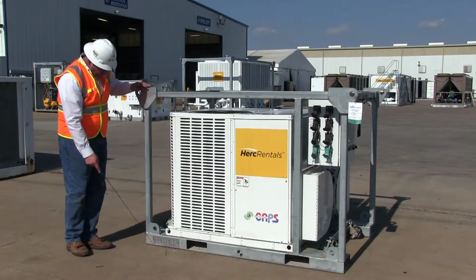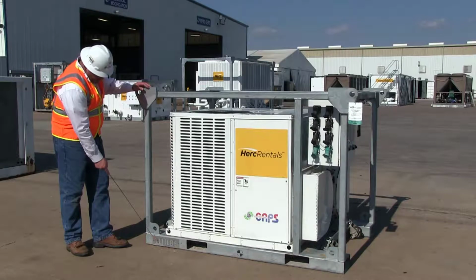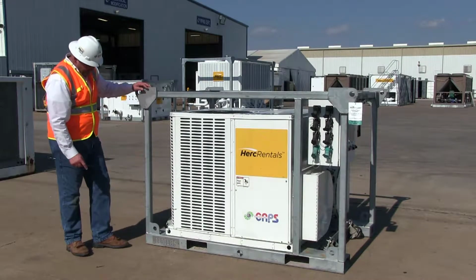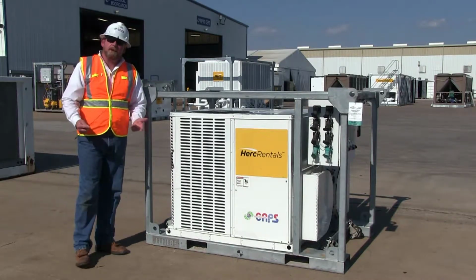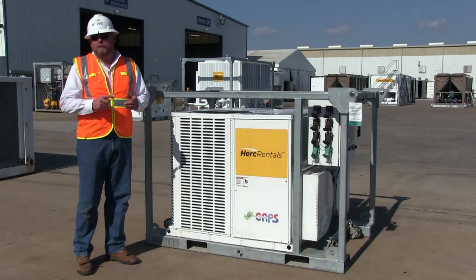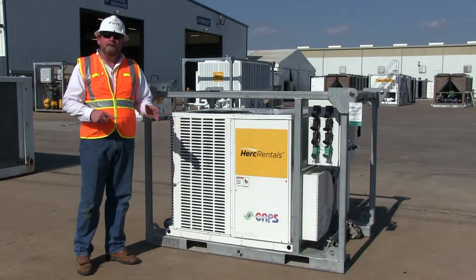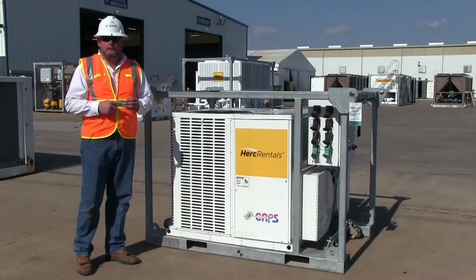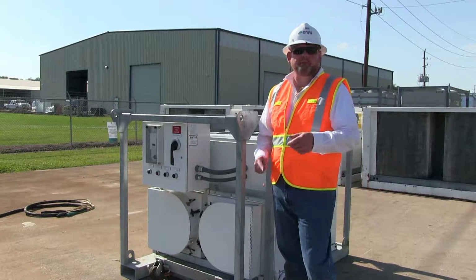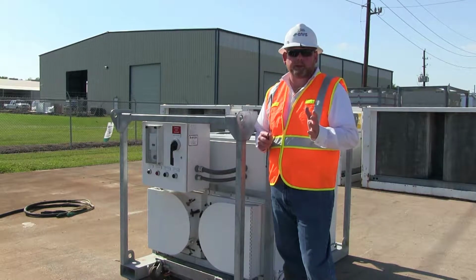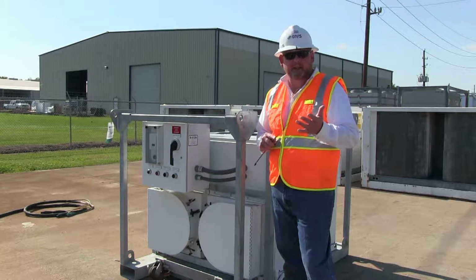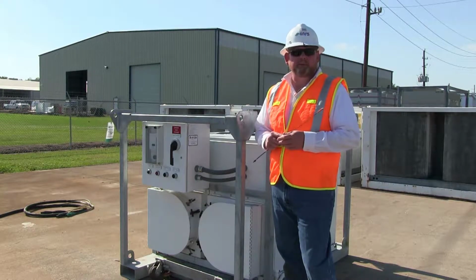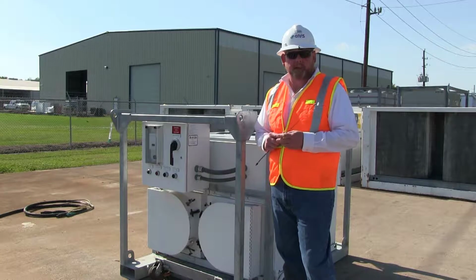And the last most important item is verifying the weight. The weight tag is clearly marked on both sides of the unit. This unit weighs 1,300 pounds, so you want to make sure that the fork truck or crane that you're using is sized properly to maneuver the unit. Since our 5-ton package unit is capable of 3 distinct modes, cooling, heating, dehumidification, you need to verify the power requirements for your particular application.